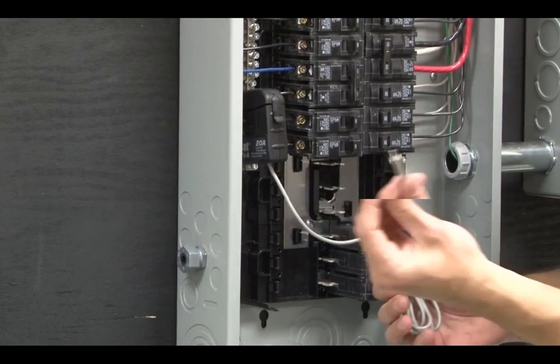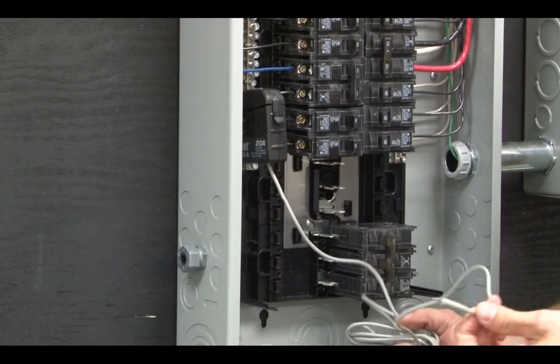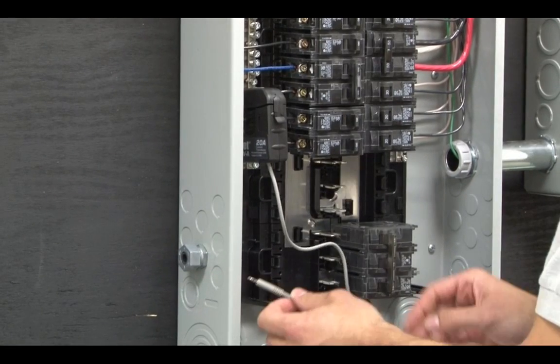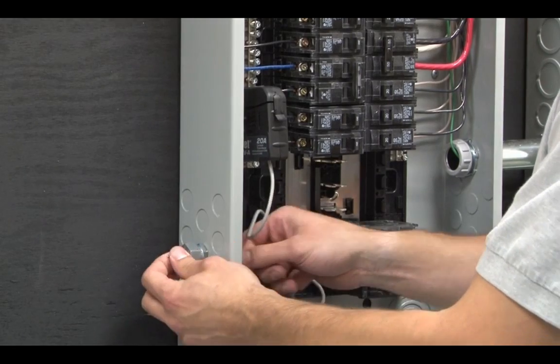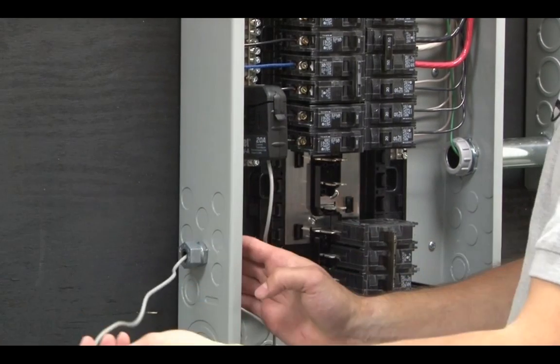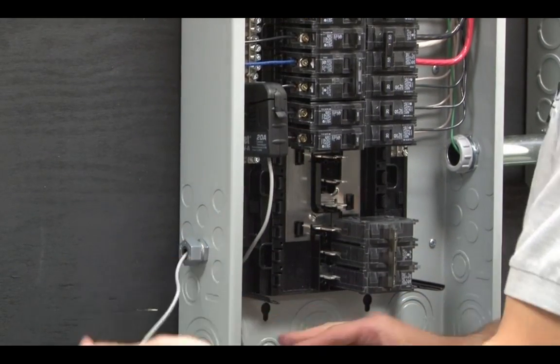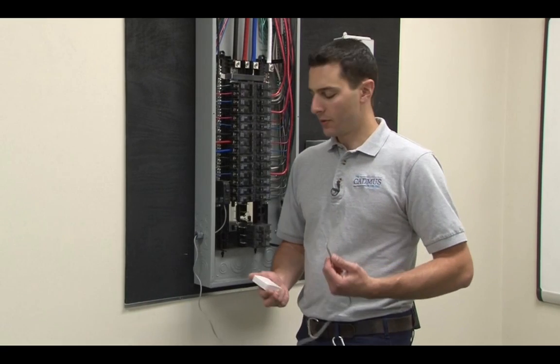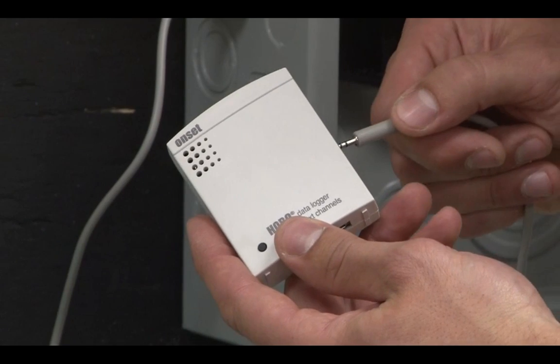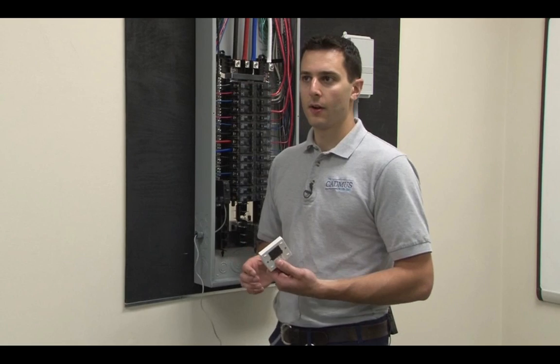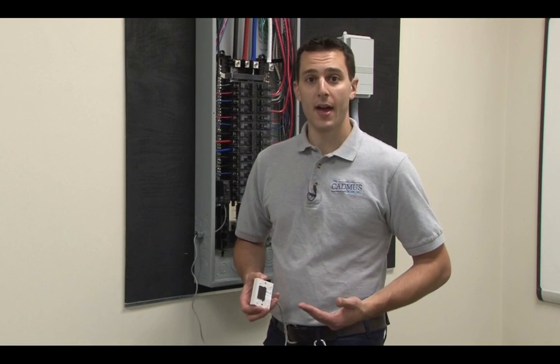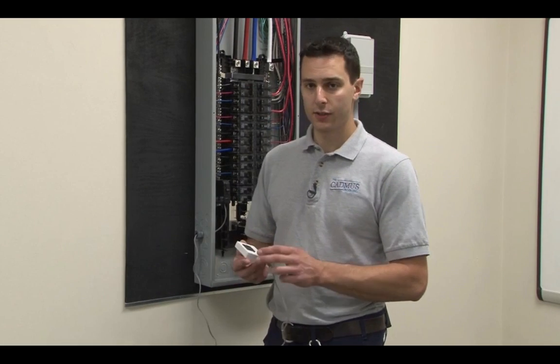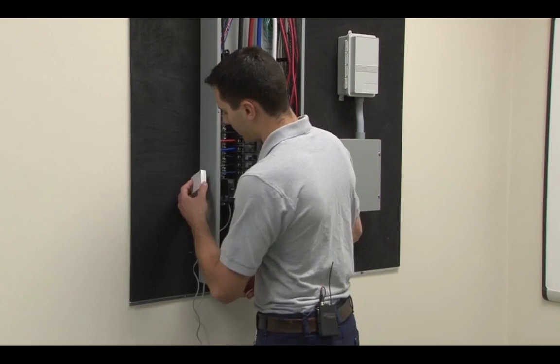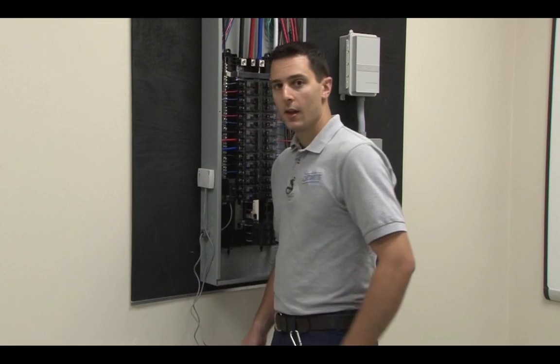Once we've identified the circuit to monitor, we'll install the CT around the conductor and line up the conductor in the center of the CTV and clip it closed. And now we'll need to run the data cable on the outside of the enclosure. We'll do so running it through this fitting. That way it'll provide a safe method of exiting the enclosure. And we will now connect the data cable to our U12 data logger. And we'll mount the data logger with one of the many methods provided with the packaging, in this case a magnetic strip. And we are now ready to launch our data logger.